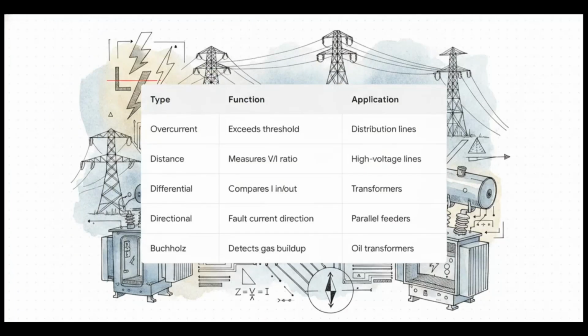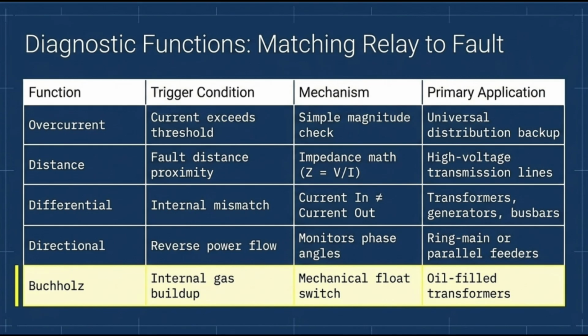So these digital brains don't just do one thing. They have highly specialized jobs, acting a lot like different defensive players in a massive playbook. Overcurrent relays trigger the moment current exceeds a preset limit. Distance relays actually use math, where Z equals V divided by I, to protect high-voltage transmission lines. Differential relays are hypersensitive. They compare entering versus leaving currents to protect transformers and generators. Directional relays keep a close eye out for specific fault current directions on parallel feeders. And one of my personal favorites is the Buchholz relay. It's a mechanical device that detects gas buildup from early-stage hidden faults bubbling up inside oil-filled transformers.